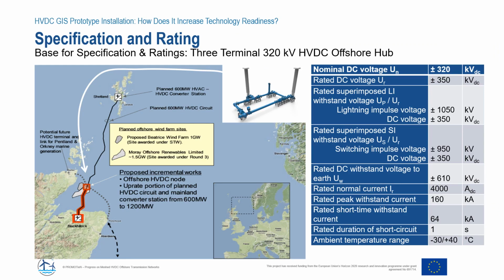In promotion, we have done this, for example, with this case study where we have an HVDC link between Scotland and Shetland, and on this HVDC link we would add some offshore wind park. And to connect this offshore wind park, we could have a 3-terminal HVDC hub offshore, and there we would need a 320 kV HVDC GIS to reduce the size of the platform. And the proposal for the test pool was to use a GIS with the ratings you see on the right-hand table, and these ratings would fulfill the requirements for such a project.